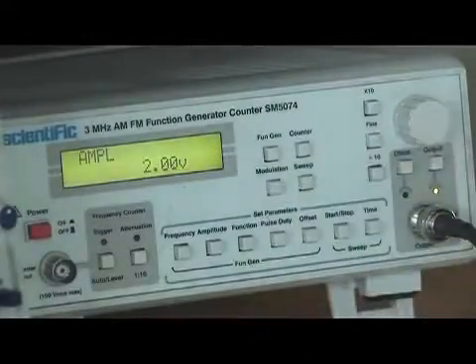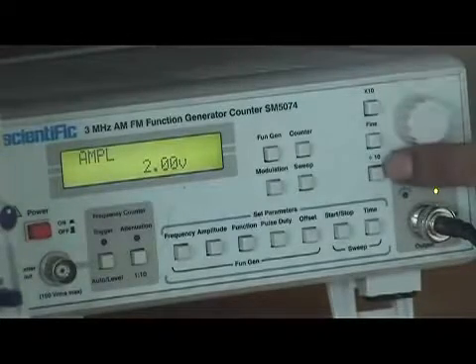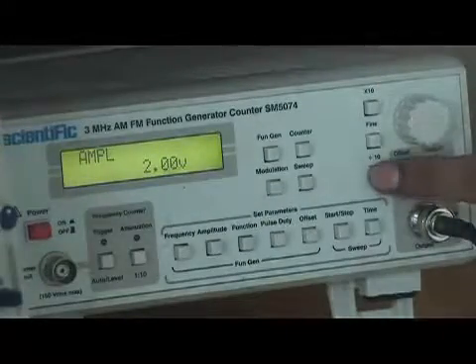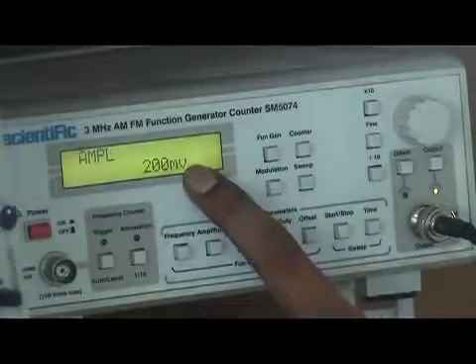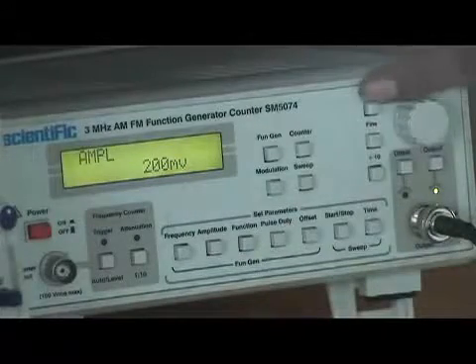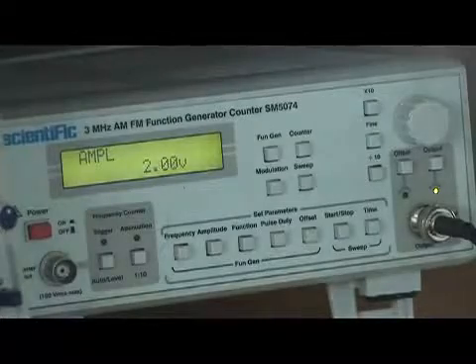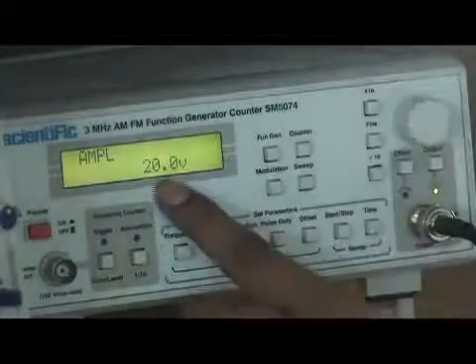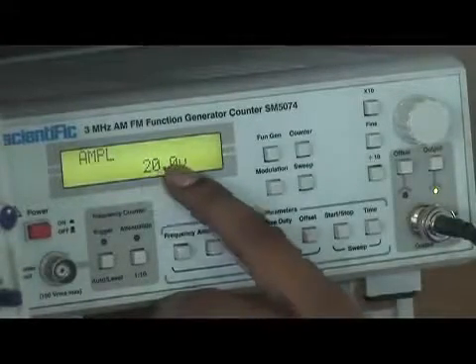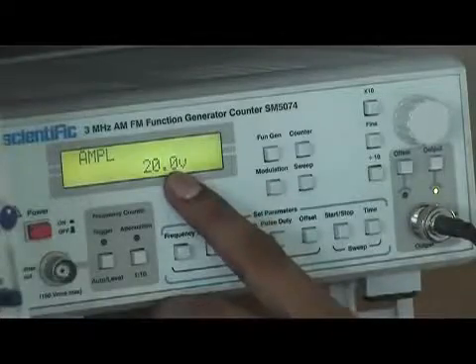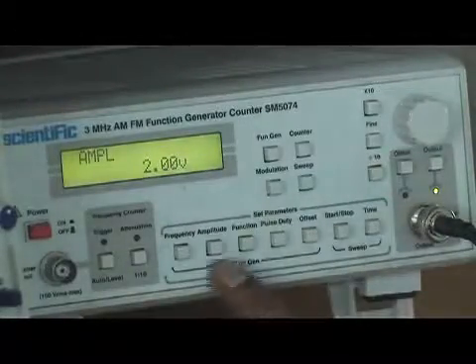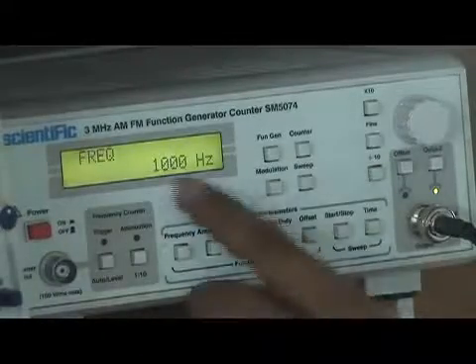If you want to make this unit in millivolts, you have to divide by 10, multiply by 10. So these two either divide this by 10 and multiply it by 10. If I divide it by 10, now you can see your unit became millivolts. Now let us come back to volts when I press this times 10. When I press this times 10 one more time, you would see the point move to 1 more times 10. So right now it will be the same amplitude 2 volt and having the frequency 1000 hertz.